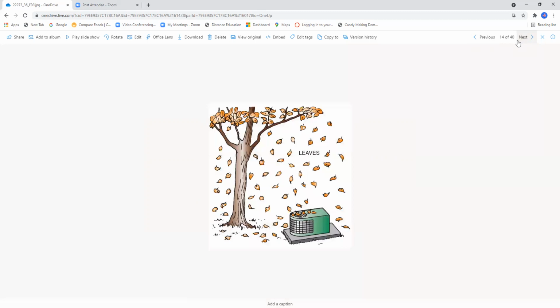And of course, we talked about this picture here where you've got the split system air conditioner and you have leaves that take and shed on here. This is found on page 1077 of your book, figure 36.30. The air conditioning unit you see here is discharging air through the top, and of course the fan blades are on top. This is a very popular design, having the fan on top and the coil on the sides. Of course, if we have leaves here, we are going to have a dirt and maintenance issue to deal with.